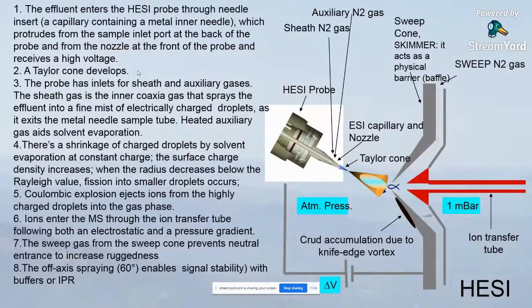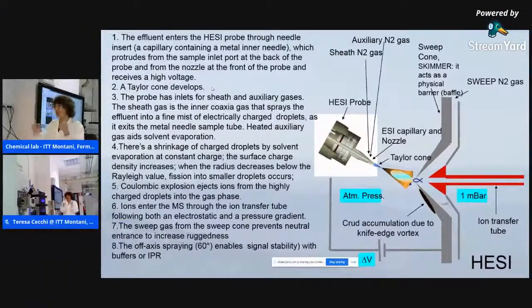And what happens? The sheath gas is the inner coaxial gas that sprays and nebulizes the effluent into a fine mist of electrically charged droplets as it exits the metal needle. And the auxiliary gas aids solvent evaporation, and there's a shrinkage of droplets by solvent evaporation at constant charge. And so the density of the charge increases, and when the radius decreases below a certain critical value, fission into smaller droplets occurs, and there's a Coulombic explosion, and ions are ejected into the gas phase.